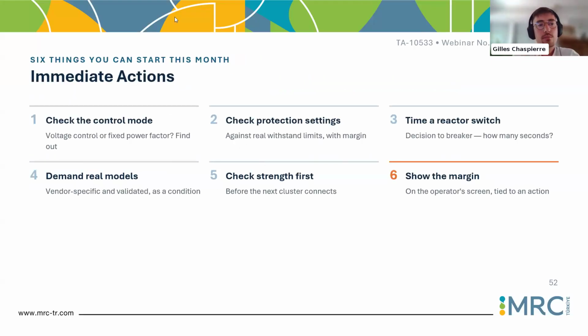Yes, next slide, please. So yeah, kind of a takeaway. It's a bit of immediate action based on these study cases that you can take with you. It's not easy, of course, but the first easiest thing you can start with is to check the control mode of your asset. Are they properly tuned to deal with fast voltage variation? If your voltage varies on a regular, intraday basis, it's not okay to have an asset that is in fixed power factor mode. It's no longer okay. It was okay 20 years ago. Today, you need to have an asset that can dynamically control the voltage.